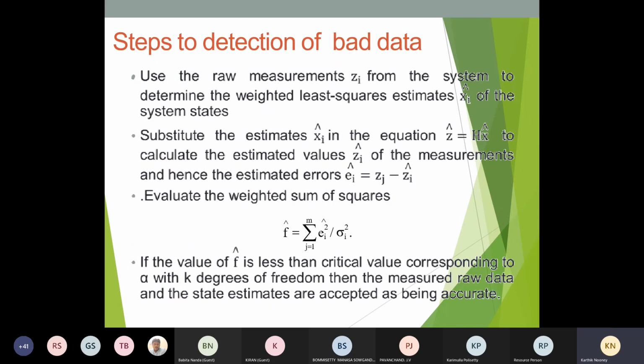We have to take the raw measurements from the system to determine the weighted least square estimate x cap. Then substitute the estimates in the equation, where the measurement matrix z cap is given by h into x cap, to calculate the estimated values of zi cap, and hence the estimated errors ei cap equal to zi minus zi cap. Then evaluate a weighted sum of squares f cap equal to sigma i equal to 1 to m, ei squared divided by sigma i squared. These are all mathematical formulas available anywhere, what I have said previously. 1 by sigma squared can be written as a weighted matrix also. Later, in the next example, I will show you how to detect the bad data.